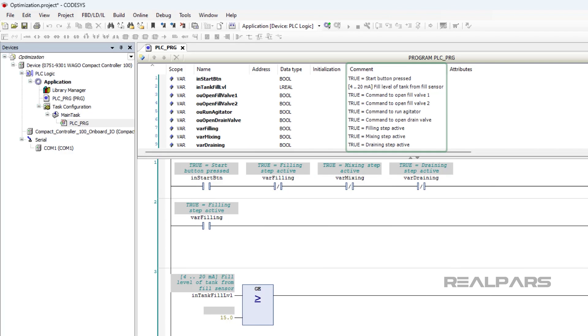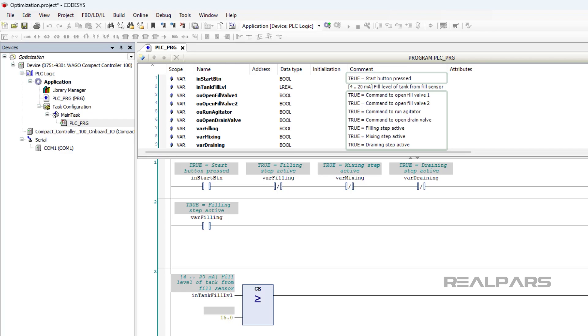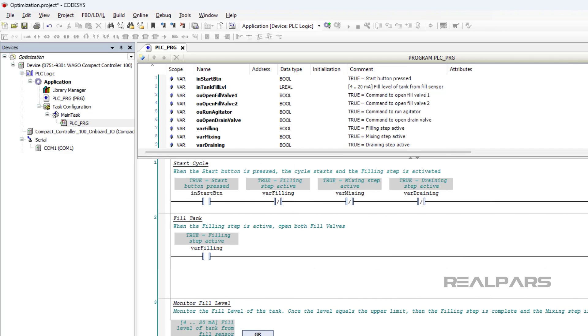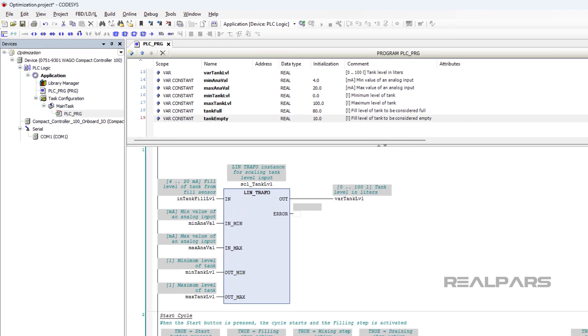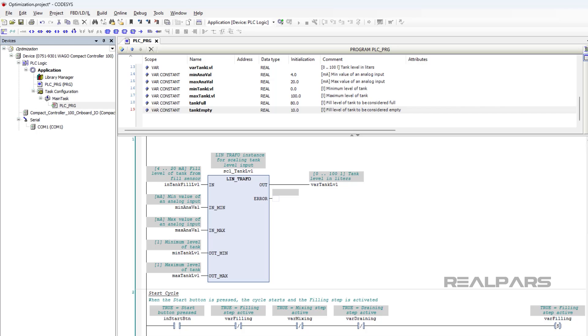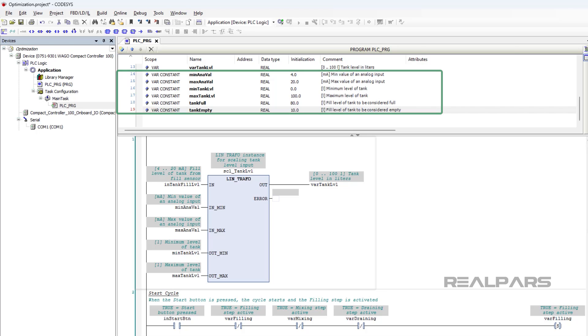Adding variable comments that provide more context about variables like the unit of measure, allowed range, and where the value for a variable is coming from. Adding rung comments that explain what is happening in the program and why it is programmed in a certain way. And making the program easier to understand by scaling raw data to engineering units and using constants to avoid the use of hard-coded values in the program.